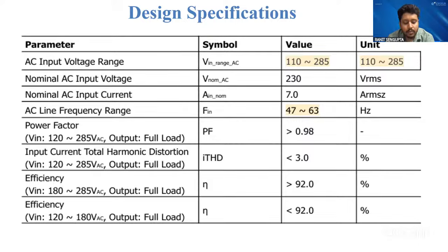So whenever we design this type of charger, we take the full load efficiency at the nominal input voltage, plus minus 10%, meaning from 200 to 250. That will give the best efficiency. But on the lower side, we are not getting that much efficiency, which is why they have written the efficiency is less than 92%.